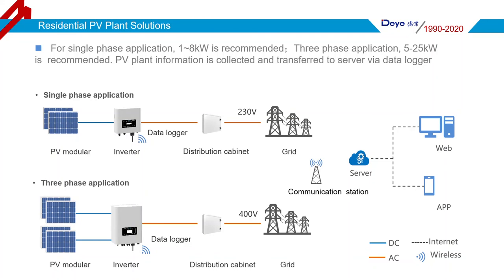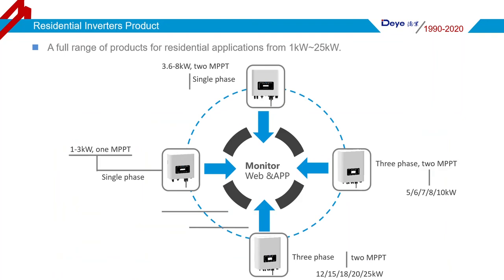For the single-phase model, we have 2 series: 1 MPPT for 1-3 KW, and 2 MPPT for 3.6-8 KW. For the 3-phase model, we have 5, 6, 7, 8, 10 KW and 12, 15, 18, 20, 25 KW models, all with 2 MPPT.